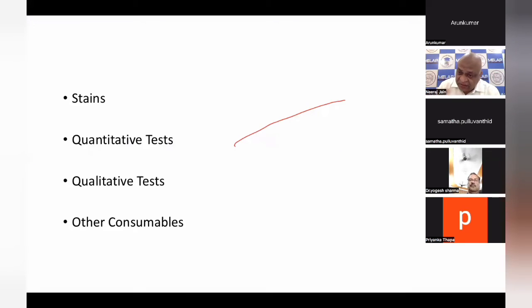For stains, these granules shall be clearly visible. For AFB, in borderline cases, it should show positivity like that. Then evidence of this acceptance testing. If you are getting some instrument printout in quantitative tests, keep that instrument printout in the record. Then some authorized person has to approve that. The procedure for lot acceptance testing, lot acceptance criteria, evidence of actual performance of this activity, and then approval by some authorized person. Whosoever is the authorized signatory for that period, that person is authorized to sign that. This is how you carry out lot acceptance testing for your quantitative test.